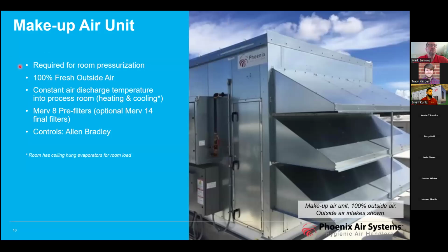Makeup air units, again, are required for two reasons: 100% outside air for positive pressure during process cycles. And it can also certainly be used for the cleanup cycle. If a client's got a very foggy application, certainly look at that 3-minute air change, and we can offer a relatively simple makeup air unit.